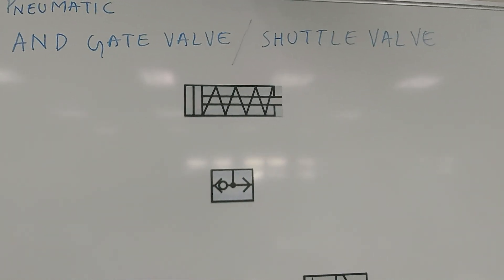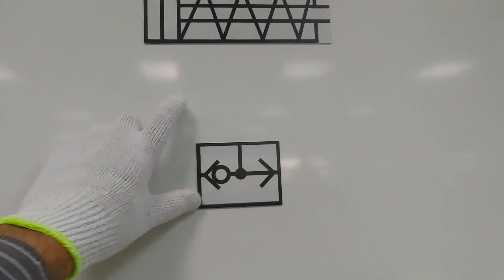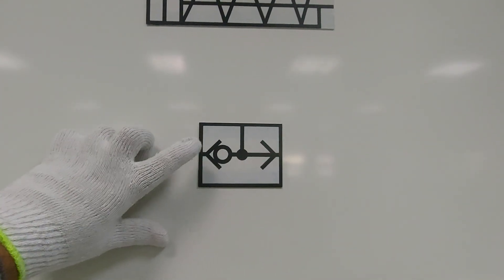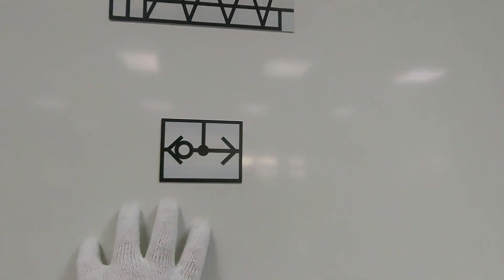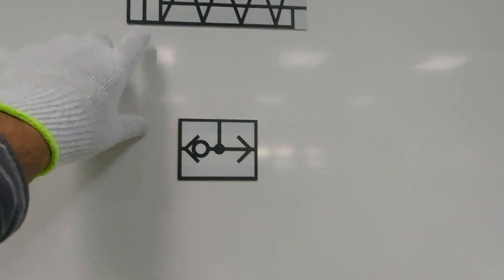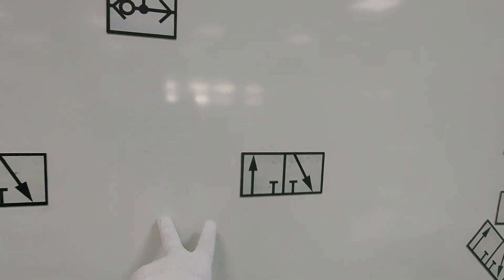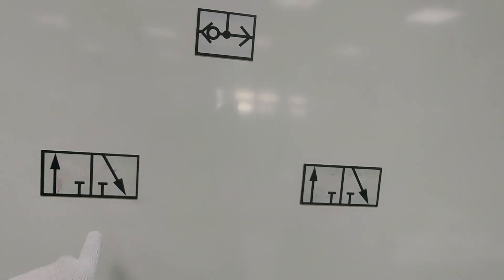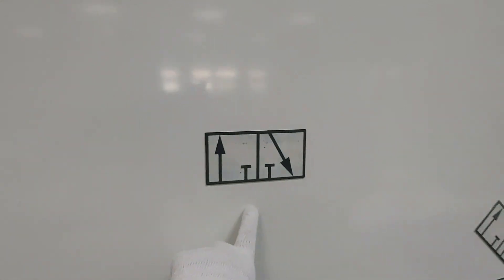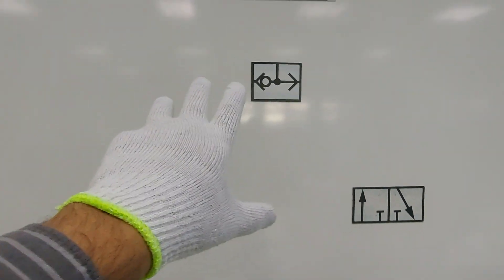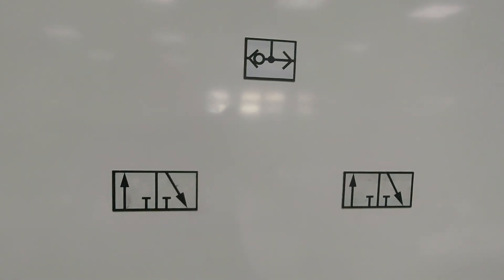Pneumatic AND gate valve, or shuttle valve. The ISO symbol for AND gate valve or shuttle valve looks like this. To connect it in a circuit we need a single acting cylinder, two valves, and direction control valves. We have used normally closed valves here. Now we will connect the circuit and then fix it on the circuit board.